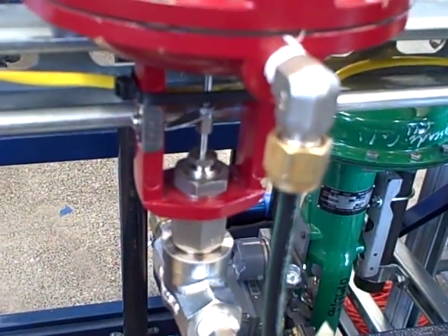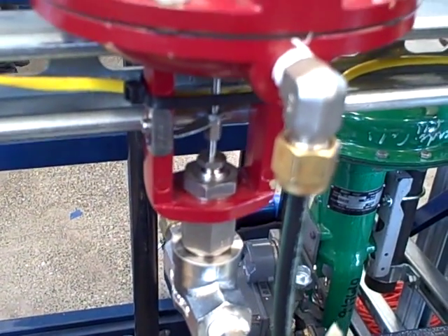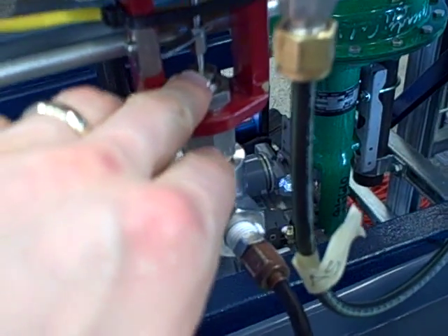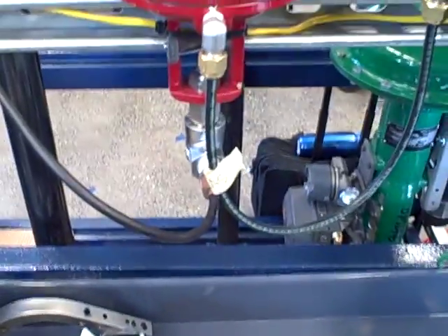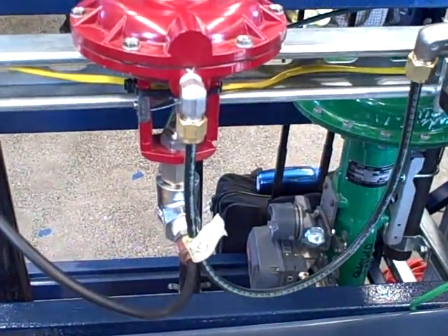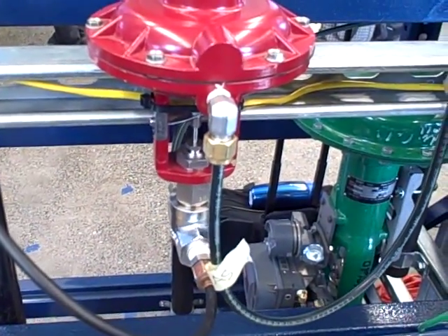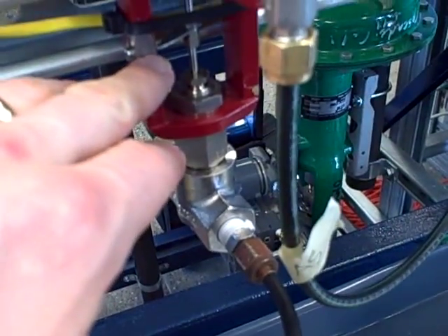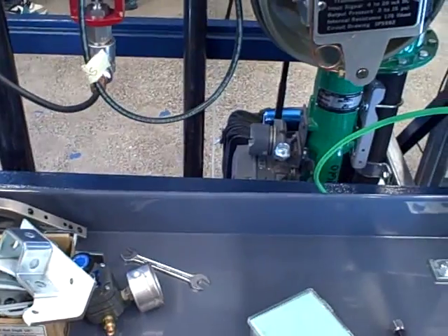As we go down towards the closed position, you notice the valve's closing off, the pressure drop across the valve increases, and as the pressure drop across the valve increases, it becomes more responsive. The same amount of stem motion has a greater change in flow rate than before. Towards the top end of the range, the process pressure across the valve decreases, so the same amount of valve motion does not produce the same amount of change in flow rate. So we have ourselves a nonlinear process.